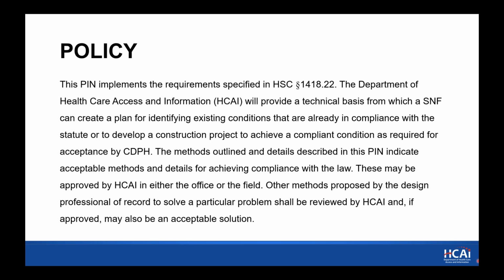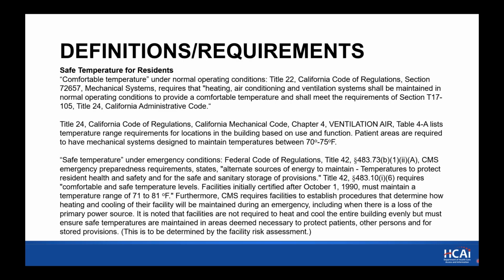So again, we're not going to tell you how to comply. We're just going to show you what the requirements are, and it's going to be up to you, the engineers, to develop a system that shows us they comply with these requirements. So a few definitions to go over. These are the definitions as shown in the PIN, but what's important here is the law requires a safe temperature. So we went back to the Federal Code of Regulations, or CMS Emergency Preparedness requirements, that define temperatures to protect resident health and safety, and for the safe and sanitary storage of provisions, to be 71 to 81 degrees. So if there's a facility that currently does not exceed the 81 degrees, they may be compliant already. Again, there will be an assessment required to show that, and we'll discuss that later.